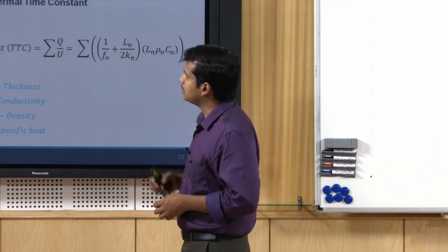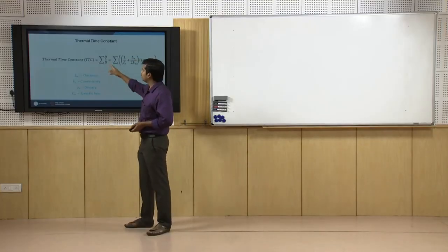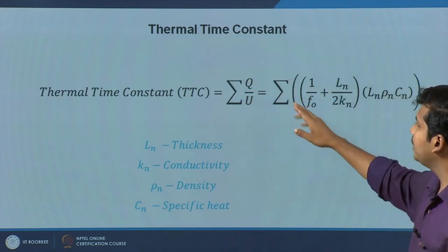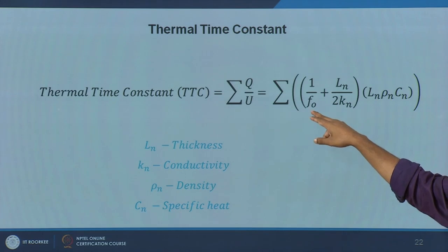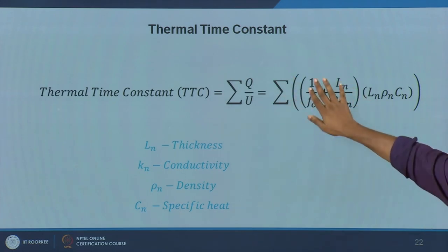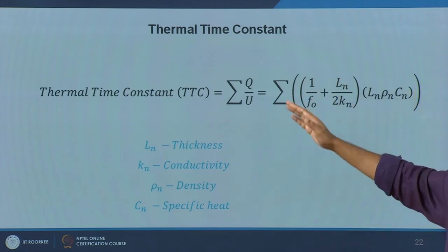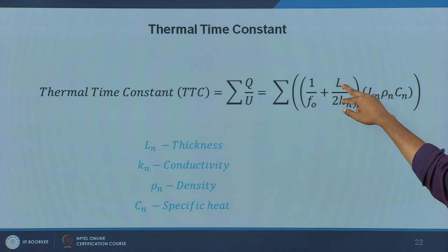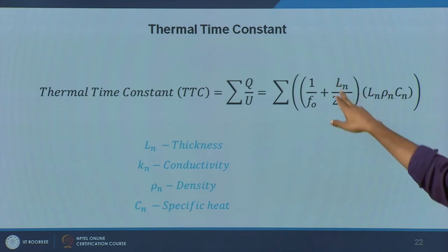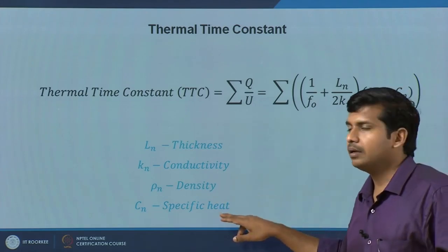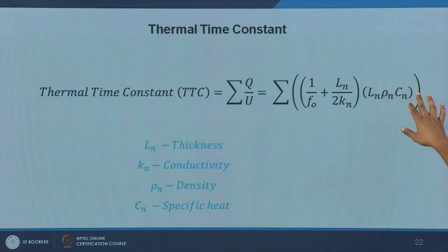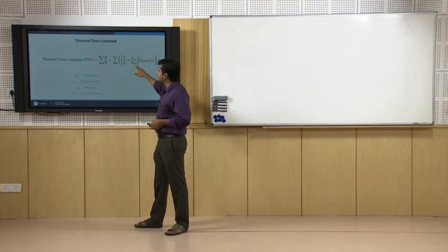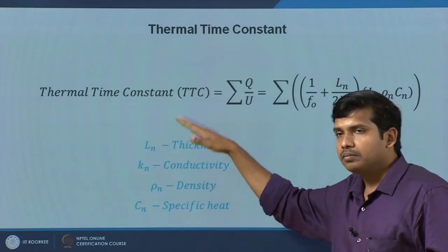The next factor discussed in the national building code is the thermal time constant (TTC). In simple terms, it is sigma Q (total heat gain) divided by the thermal transmittance U-value. It involves the surface coefficient, thickness, conductivity — effectively giving thermal resistance — plus density and specific heat. As density and specific heat increase, the thermal time constant goes up. As wall thickness increases, the thermal time constant also increases.